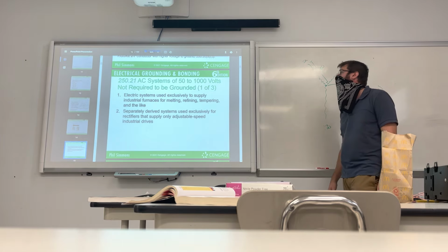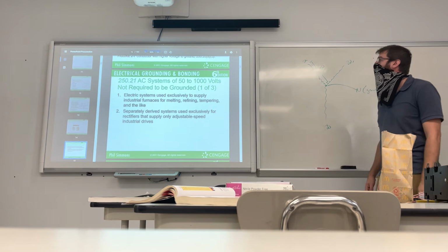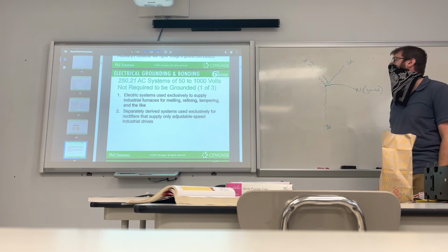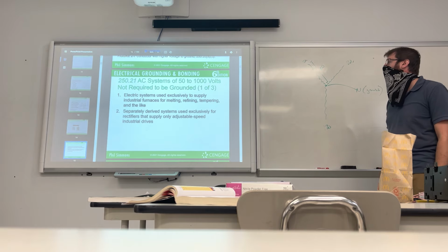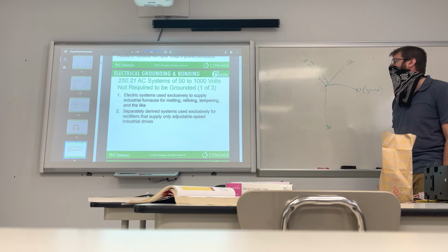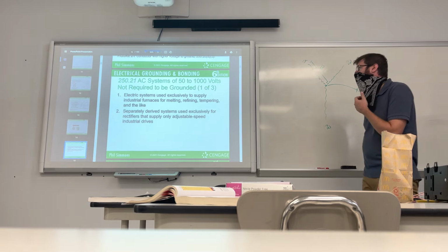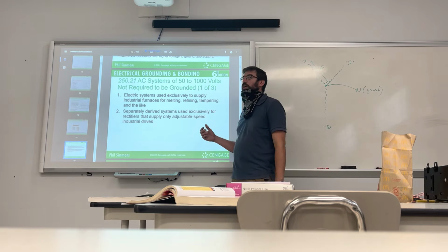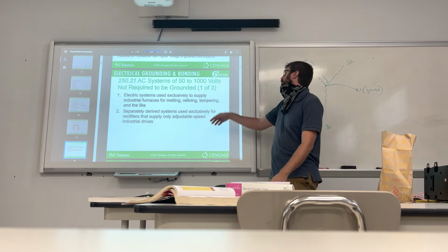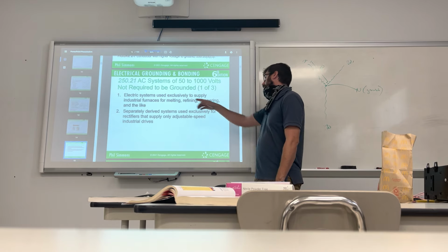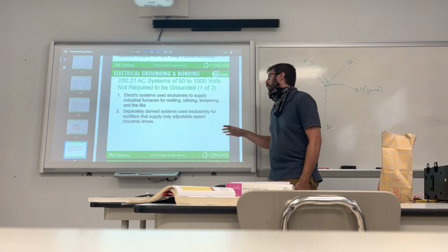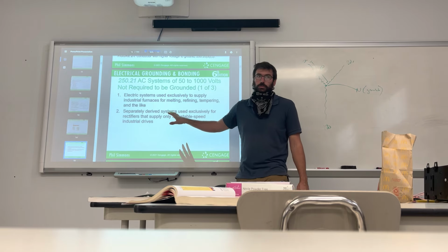250.21: AC systems of 50 to 1,000 volts not required to be grounded. Electrical systems used exclusively to supply industrial furnaces for melting, refining, tempering, and the like. Separately derived systems used exclusively for rectifiers that supply only adjustable speed industrial drives. And that's just what I was talking about. We're talking about big things like industrial melters, huge boilers, furnaces, which is the same thing as a boiler, or running huge motors with motor control systems.